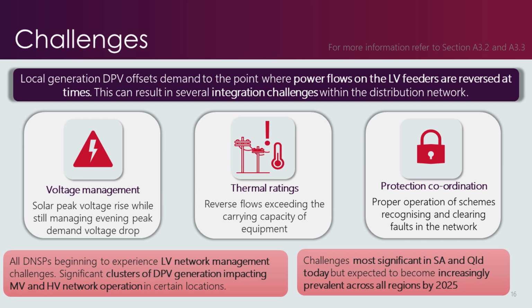The next challenge is managing the actual power flows in the network. This needs to be within permissible loading levels of different network elements and basically determined by how hot equipment gets, so referred to as thermal ratings. Typically, DPV systems along a street will experience the solar peak at the same time in the middle of the day when the sun is shining brightest. With peak demand in the evening, there is generally a level of diversity across different end users. Not all are likely to have their air conditioners on at the highest setting at the same time, for example. This means that the solar generation peak can occur more frequently than the peak demand one, which typically only occurs a handful of times a year.